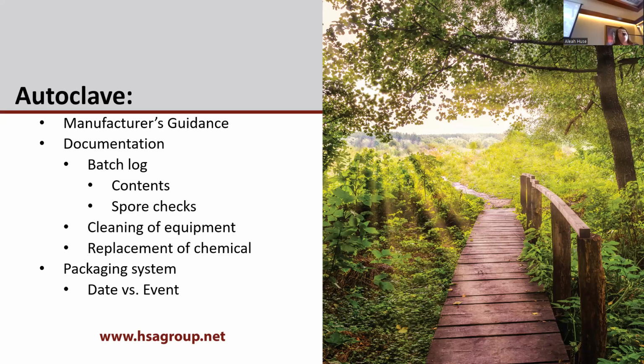Commonly, the things that we find missing, and my colleague Michelle is here with me today, and she does quite a few walkthroughs as well. But when we do an initial mock for a clinic, the things that we find when they have an autoclave is missing documentation. They're not doing the spore checks according to manufacturer's timelines required. They don't have a batch log to show what instruments were processed when and what packaging system that's going to be related to. Because if that spore check comes back inaccurate, you should be able to pull the supplies that were run through that and be able to reprocess them. And how do you do that if you don't have documentation?